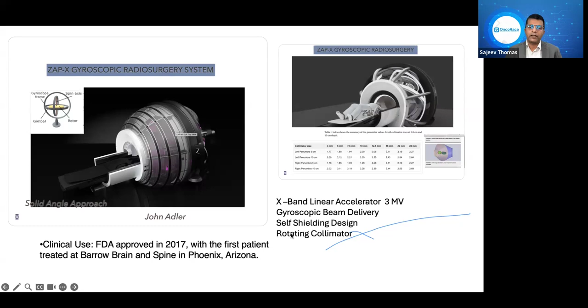It is dedicated to brain and head and neck stereotactic radiosurgery, and it uses an S-band linear accelerator and integrated minimal shielding, so it does not require a radiation bunker. At the core of the ZAP-X system is a compact gyroscopically suspended treatment head mounted on a dual axis rotational frame. This enables the delivery of non-coplanar beam trajectories without moving the patient couch. This allows highly conformal dose distributions. The gyroscopic mechanism allows the treatment beam to pivot in spherical arcs around the isocenter with exceptional mechanical accuracy.